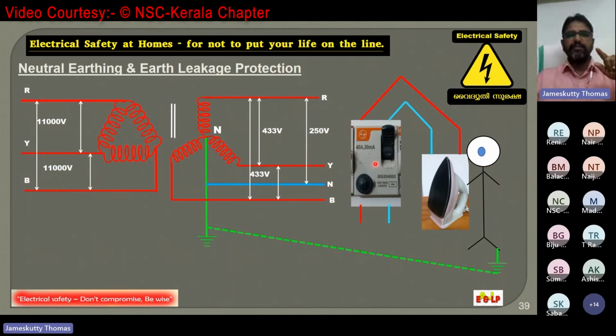Similarly, here in this diagram, it will be checking the inward current. See, this is the phase conductor and this is the neutral conductor. So it will be checking the inward current and the outward current. Phase and neutral are wired through this RCCB. You can see there is an internal coil inside this RCCB which constantly checks whether the inward current and outward current are equal. Say 1 ampere of current is going into the phase wire and returning to the source through the neutral. 1 ampere going in and 1 ampere coming back. If both currents are equal, the circuit operation will be stable, which means the circuit will keep working.